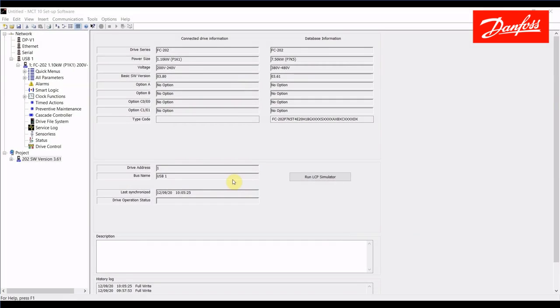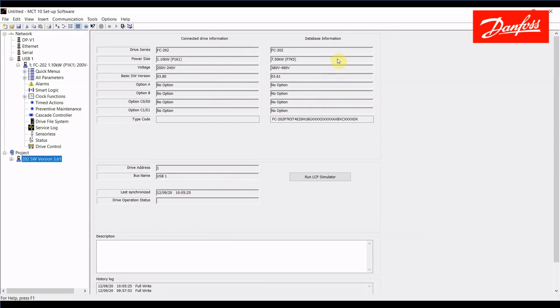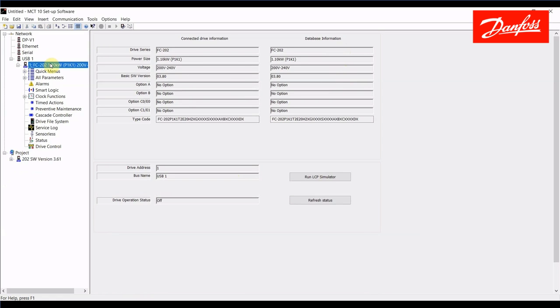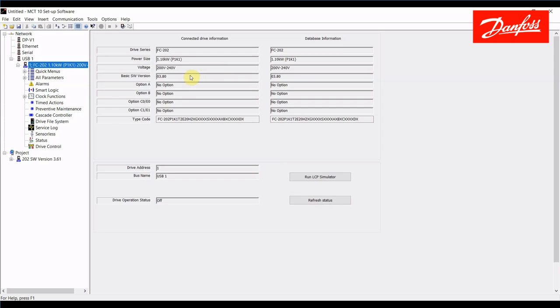Okay, so let's get started. The first thing I'm going to do is show you how to write an existing project file. I have one saved here. It's for an FC202 AquaDrive, it's a 10 horsepower, 480 volt with software version 3.61 and I'm going to write that project file to the drive I am connected to over here on the USB that is also an FC202, however the power size does not match. This is a one and a half horse drive. The input voltage does not match. This is a 240 volt drive and the software version is current 3.80. So we have a newer software version in the actual drive I'm connected to as well.